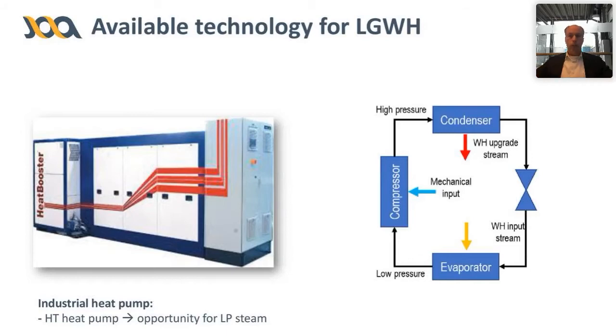So the industrial heat pump, how do we apply this? Nowadays, more and more high temperature heat pumps become available. And if we are talking about drying processes, we are getting, for example, recovery streams of 85 degrees Celsius. This heat can be used to generate low pressure steam. Many processes in the industry are driven by steam. Let's say the thermal energy input is by steam. In many cases, the steam pressures in the plant are, for example, 8 or 10 bars.